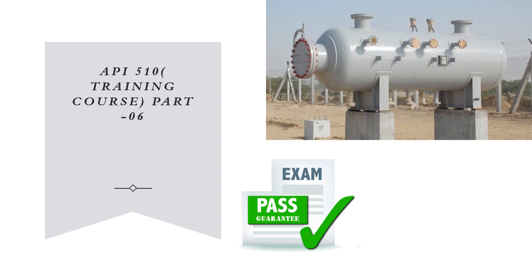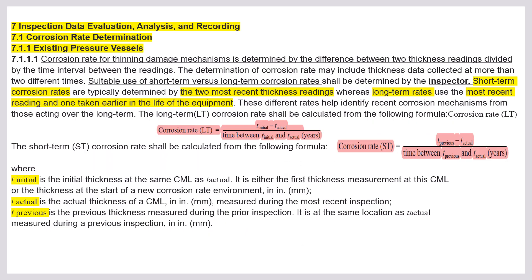What is inspection data evaluation? The corrosion rate of a thinning damage mechanism is determined by the difference between two thickness readings divided by the time interval between the readings. I will make it simple: when you put a pressure vessel in service, you find the initial metal thickness of the steel plate.